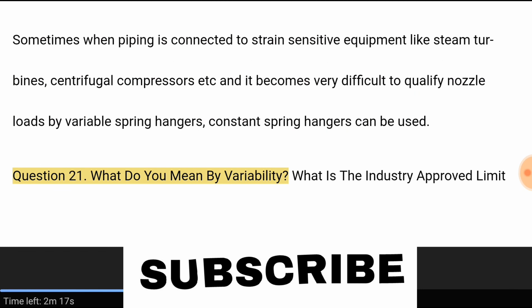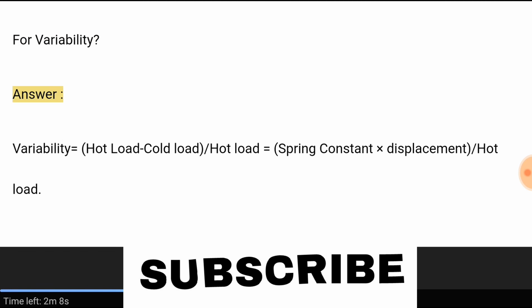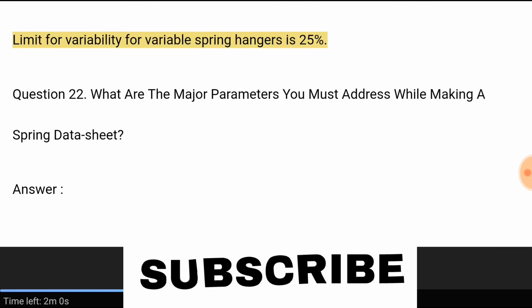Question 21. What do you mean by variability? What is the industry-approved limit for variability? Answer. Variability equals (hot load minus cold load) divided by hot load. Hot load equals spring constant times displacement plus cold load. The limit for variability for variable spring hangers is 25%.